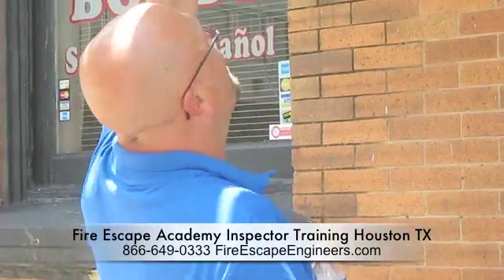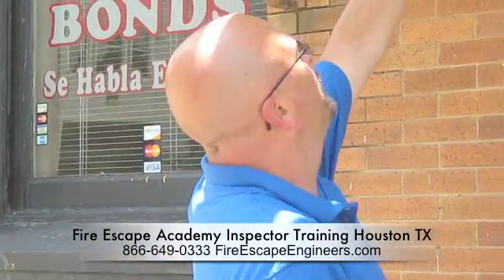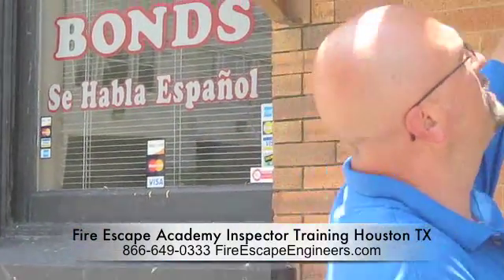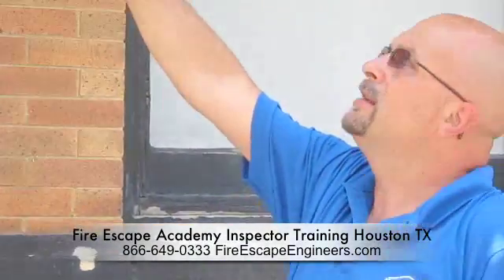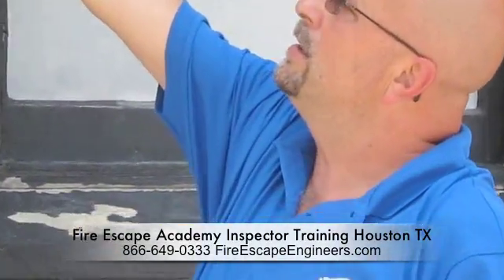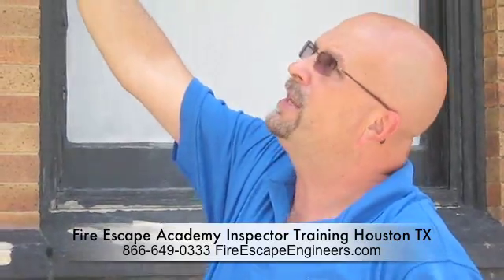I've got deterioration on all the paint, and then some of the joints, some of the treads. Another thing you can clearly see — it's important to notice the tears, the tears of rust that come from the tread connection, so that means some of the treads are in bad connection.